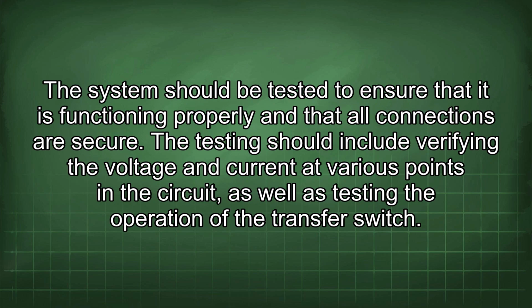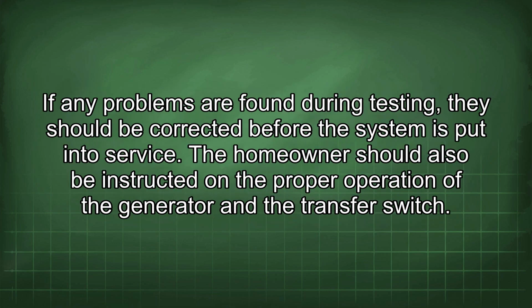The system should be tested to ensure that it is functioning properly and that all connections are secure. The testing should include verifying the voltage and current at various points in the circuit, as well as testing the operation of the transfer switch. If any problems are found during testing, they should be corrected before the system is put into service.